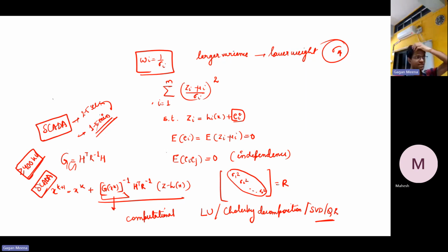So using the hybrid state estimator can help in improving the accuracy of state estimation. Also, it will increase the observability because now we have more measurements from SCADA. And because there are more redundant measurements, bad data detection and handling also becomes easier, as we have different sources of error in state estimation: modeling error, data error, and transducer and sampling error. All these things we also discussed.